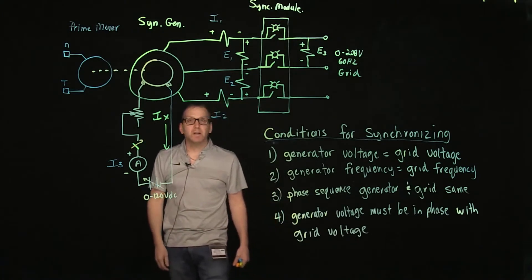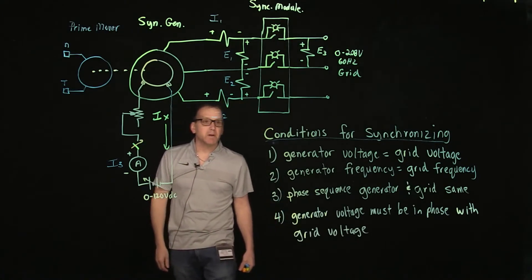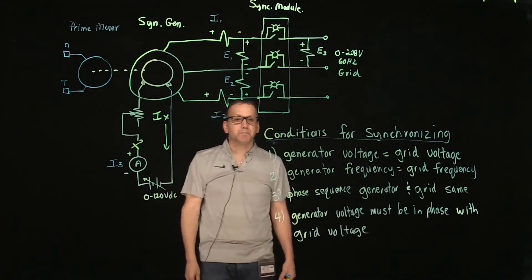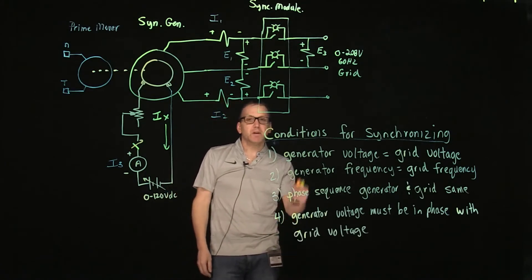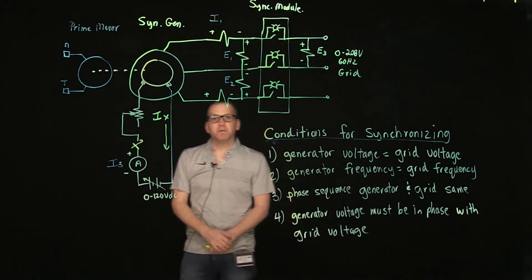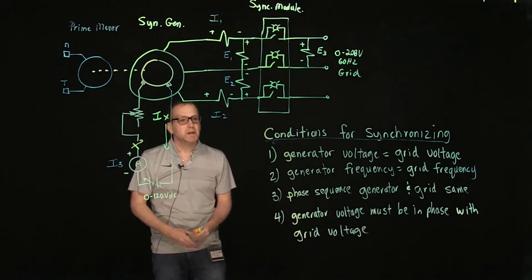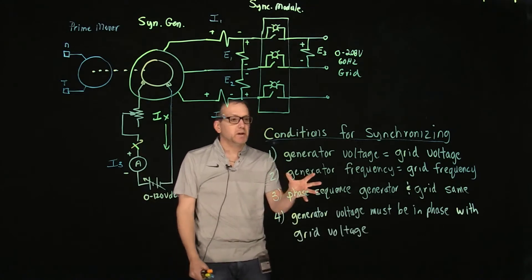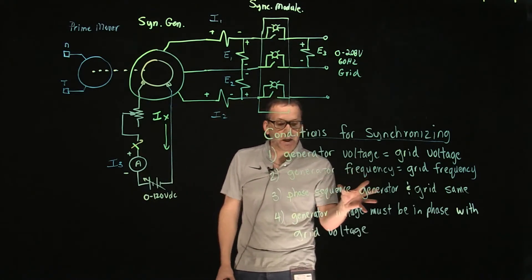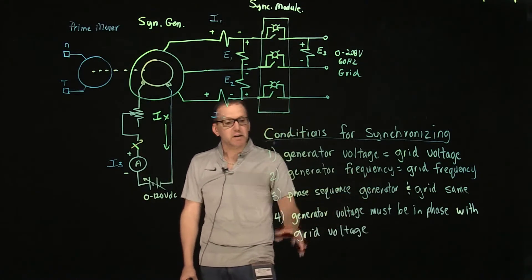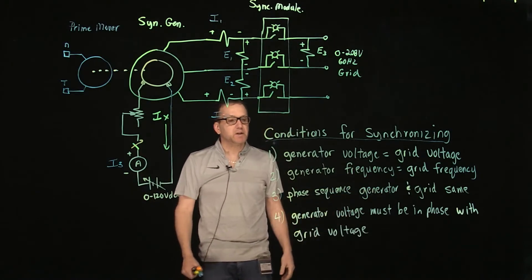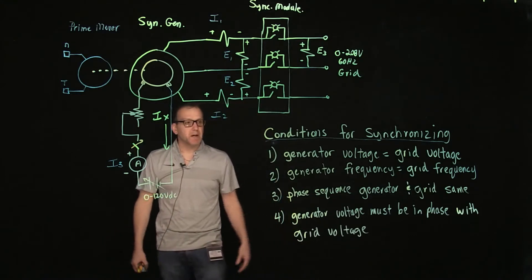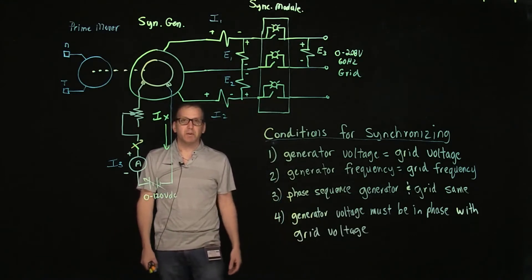The conditions are: the generator voltage must equal the grid voltage, the generator frequency must equal the grid frequency, the phase sequence of the generator and the grid must be the same, and the generator voltage must be in phase with the grid voltage.